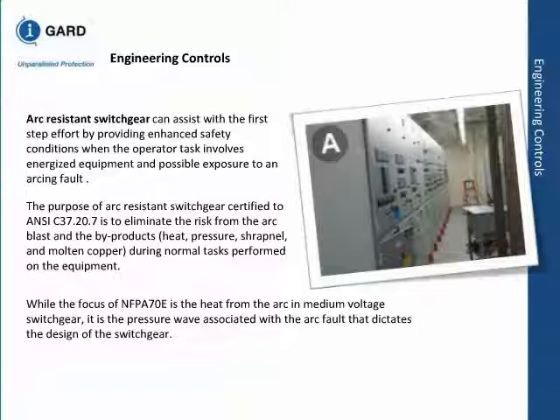Standard switchgear, though nothing is standard of course, has been tested on a bolted fault and has not been tested on an arcing fault at all. When you have a bolted fault, the only thing you have is mechanical stresses, so the door would not see anything. When you have an arcing fault, you will see a tremendous amount of blast pressure, and the door will blow away. This is the reason you need arc-resistant switchgear, because the door is reinforced to allow the arc to dissipate from the top of the cubicle to protect the person.